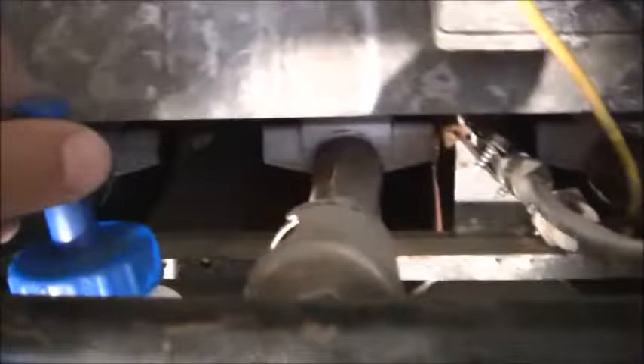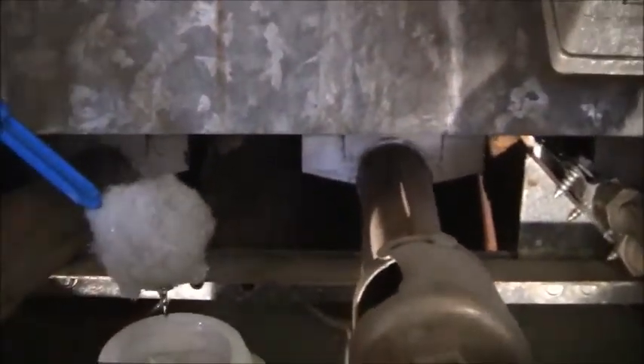Now I'm going to take my big blue, Brush On Blue, which is a leak detector. I'm going to take that and put it around the two joints that I disturbed. What I'm looking for is bubbles. I am looking for bubbles to tell me that I have a leak.